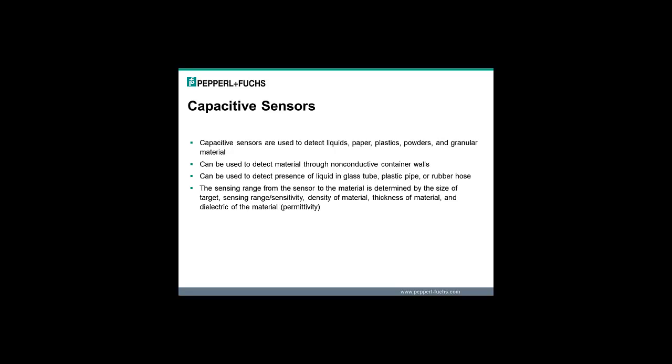They can be used to detect liquid material through non-conductive container walls. They can also detect liquid in a glass tube, plastic pipe, or rubber hose. The sensing range from the sensor to the material is determined by the size of the target, the sensitivity, density of the material, thickness of the material, and dielectric of the material.